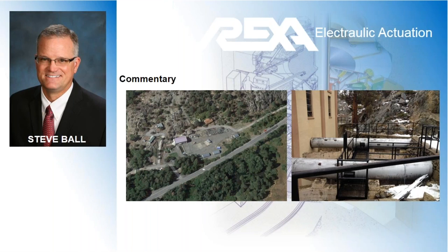What we thought was, if we had an ability to open up the needle a little faster for frequency recovery, what we would call load acceptance, that would be greater flexibility to the connected load. In other words, our recovery would be faster. If you lose tie to the system and you have more load present in that local area than what you were running water for, you can put more water to the turbine and have a faster recovery of frequency and, of course, voltage control.